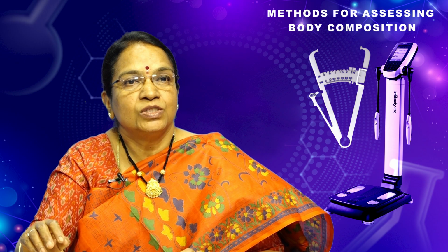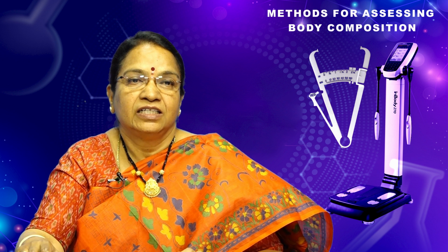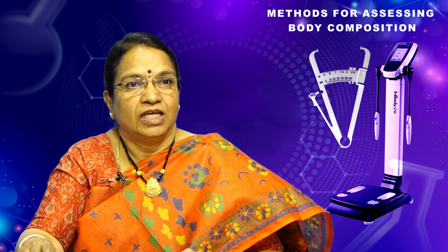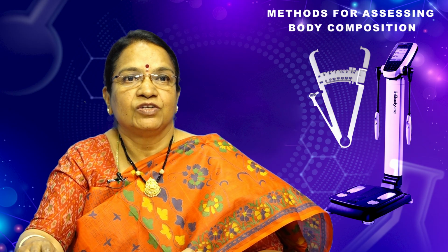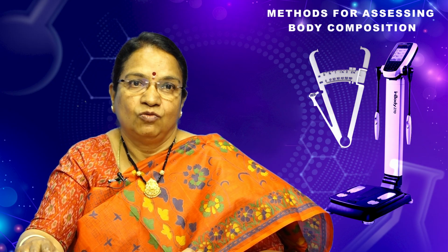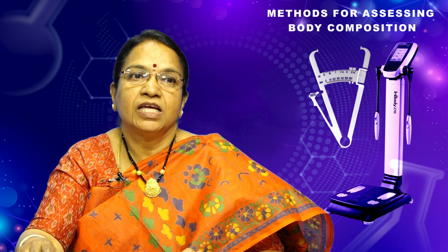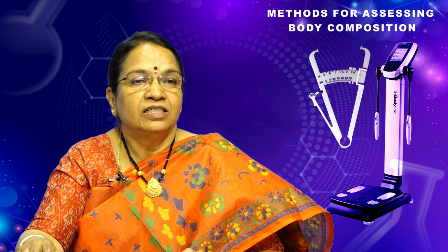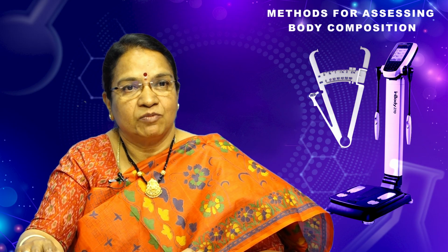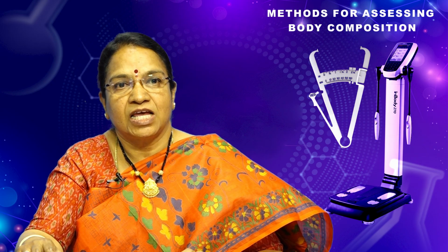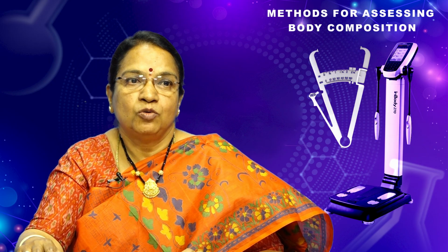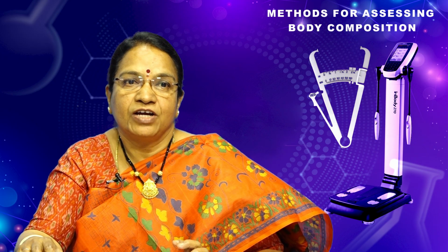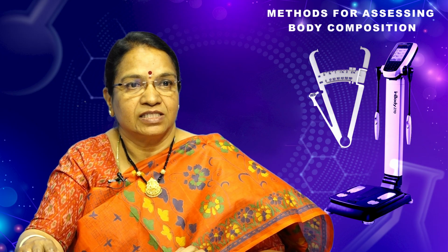Then, using the basic understanding that density equals mass over volume, a person's mass is recorded with their body weight. Volume is measured using air displacement in the BODPOD. Since both fat mass and fat free mass have known densities, the BODPOD can estimate how much fat and how much fat free mass a person has.